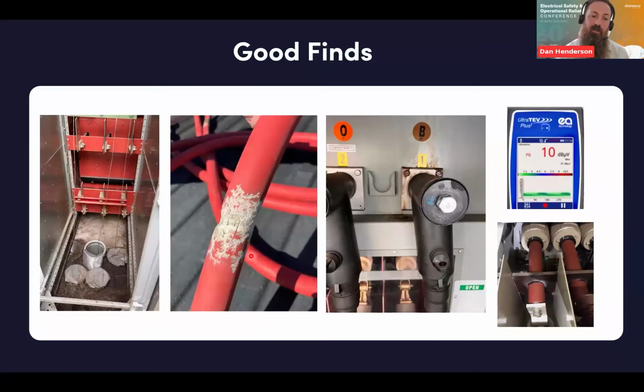Another external switch, which was again given a 5-year condition assessment. Within 3 years, they were getting PD readings on there, and that was the cable within the switch. So again, this is where, as in that first example, it was reduced down to 3 years. That was brought into 36 months purely because they needed to ensure that integrity was correct before they moved it back to 5-year. On this example, this was a thermography identification on a 13.8 kV transformer. You'll see there the nice shiny phase in the middle, and then this phase here where you start getting the burning and the discoloration. So that temperature differential was clear, and that allowed us to plan in a downtime which was convenient with the business, investigate, and then repair and get it back online before any downtime, similarly in a CT chamber. So these are good examples of where you can pick things up using these predictive tools or things that are at your disposal as part of your inspections, and catch them before it leads into a catastrophic failure.